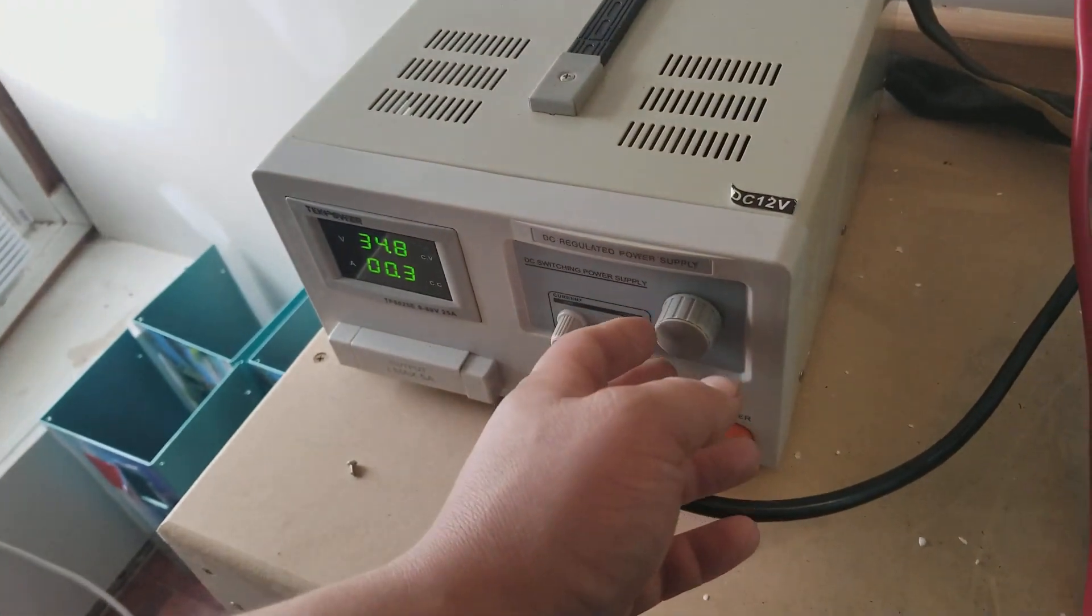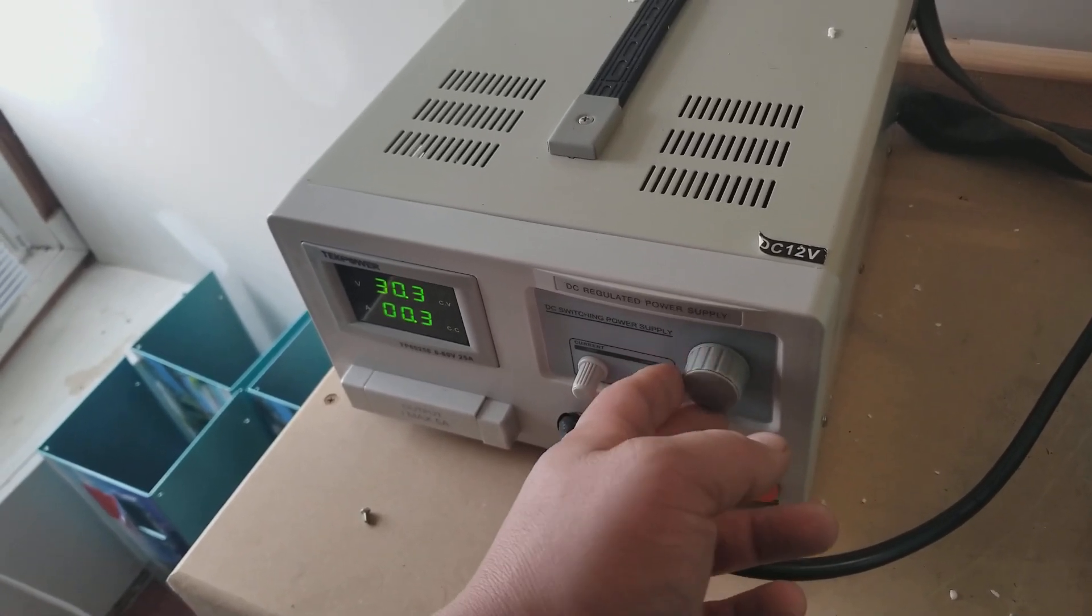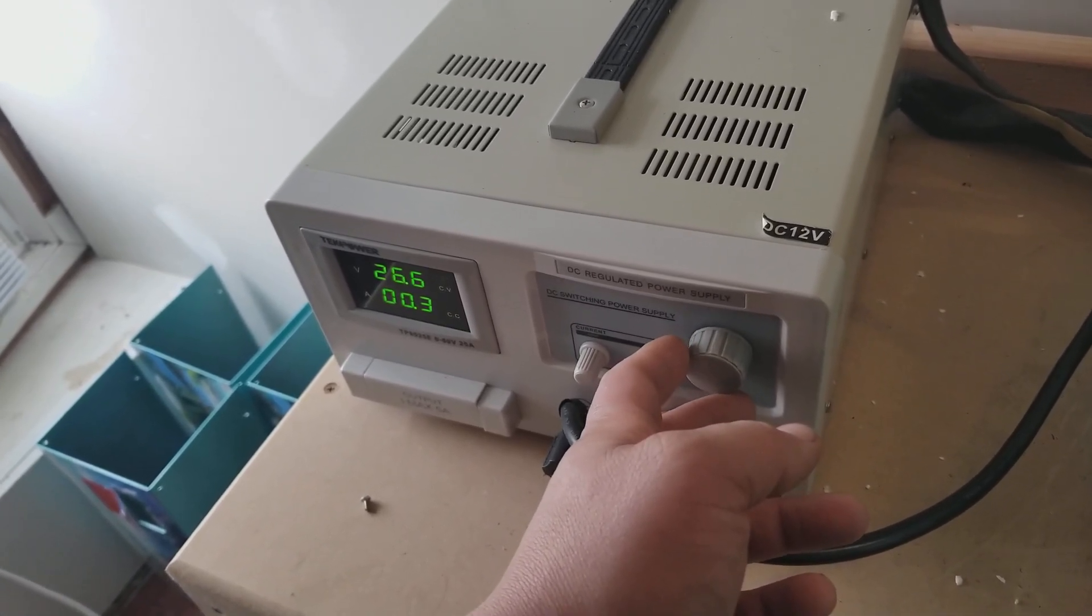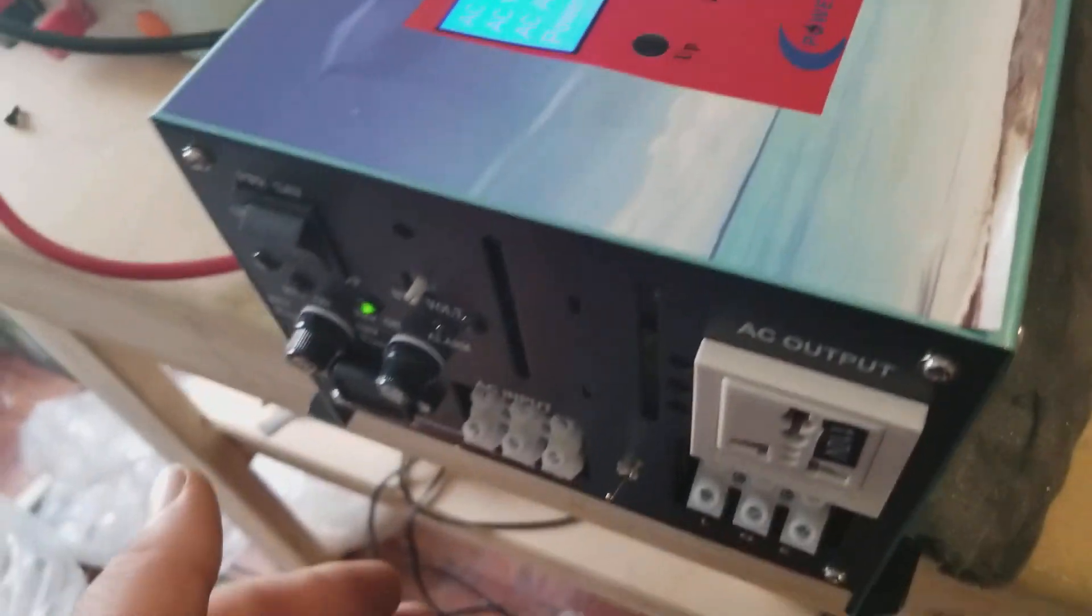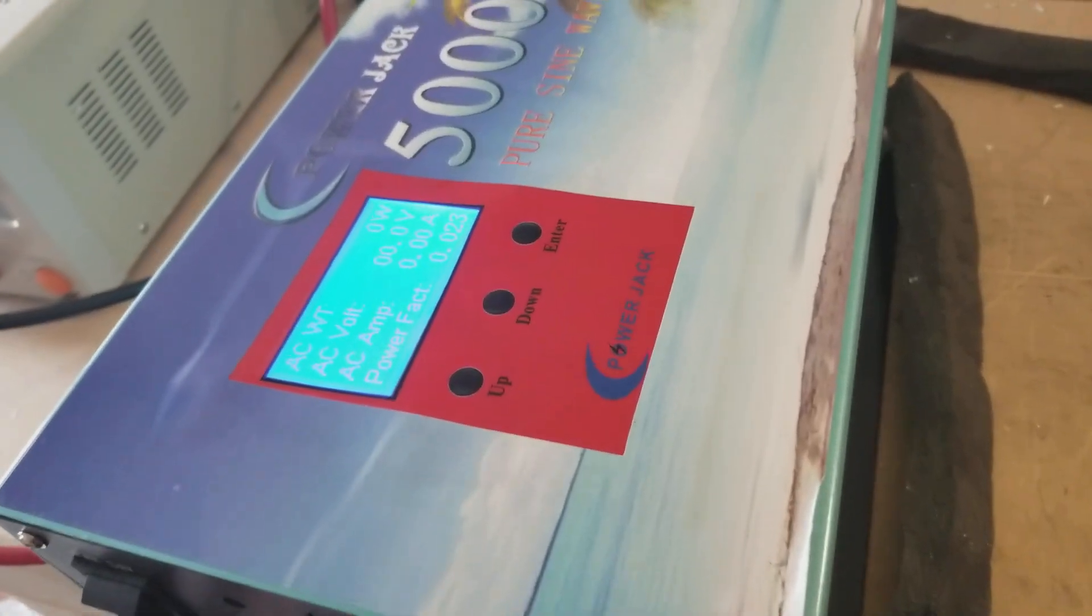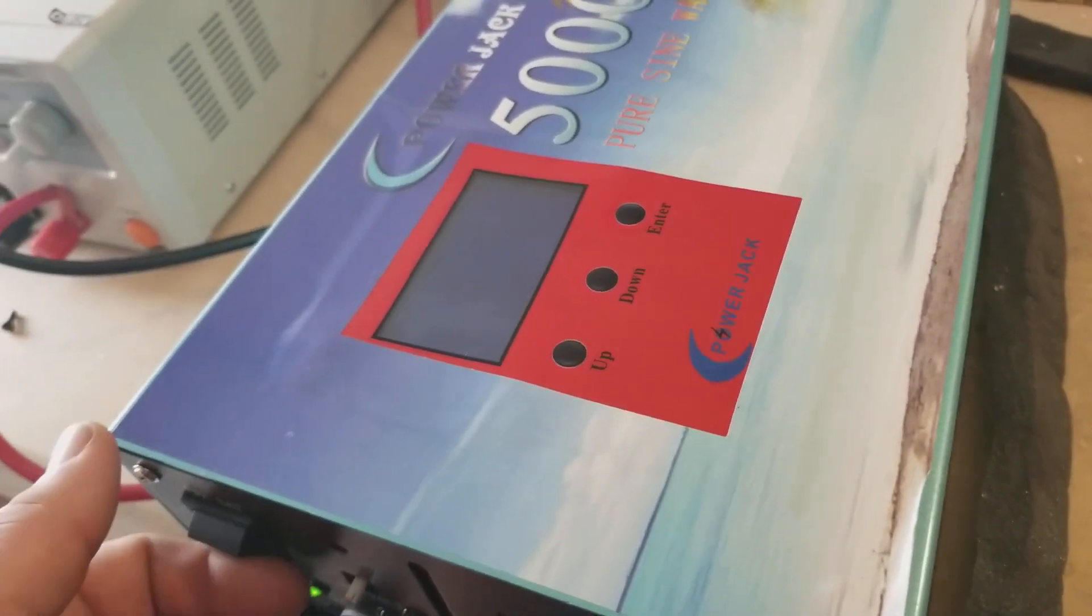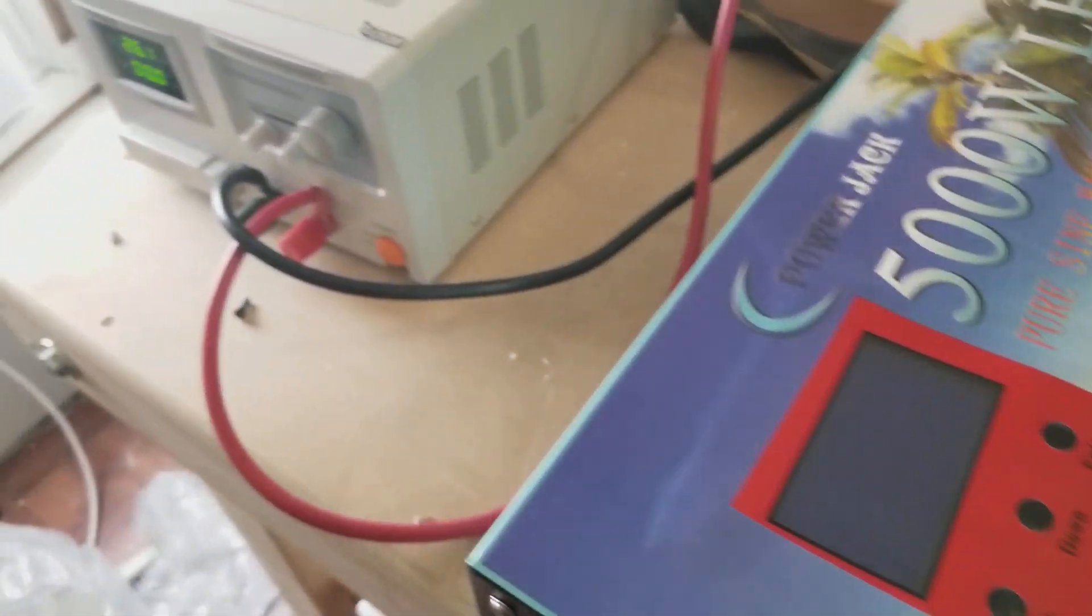And this is, you cannot recover from this. You come all the way back down to, let's say, 26 volts, the inverter stays in alarm mode. So it's not like it's going to pick itself back up. So if you're away from the inverter and you don't hear this, that's going to be your problem. So in other words...